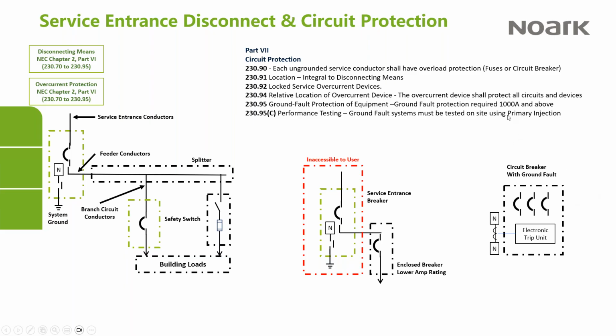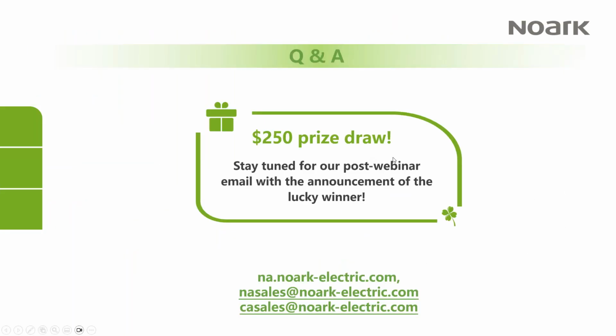The primary injection testing means that if the breaker has a push-to-test button that electronically makes it trip, that's not acceptable. What you need to do is actually inject the full current through the primary side of this sensor. Okay, and that again is a relatively misunderstood clause in the code, and we've actually got an instruction for our air circuit breakers to help people understand that. And that's it for the technical part.